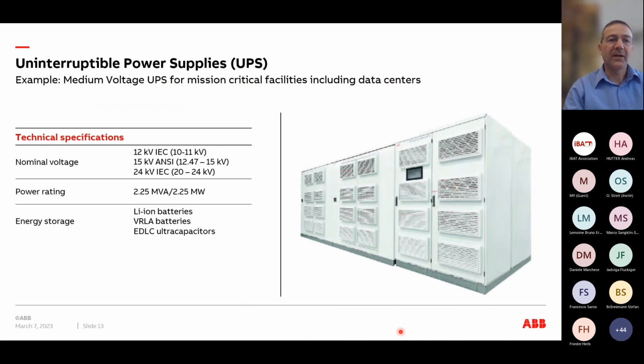One large example is a medium voltage UPS - a big cabinet that includes the batteries too. It can be lithium ion, valve regulated lead acid, or supercaps, but in most cases it's actually still lead acid. These solutions are used a lot - for example, I think a hospital uses one of these, and also banks and industrial customers.